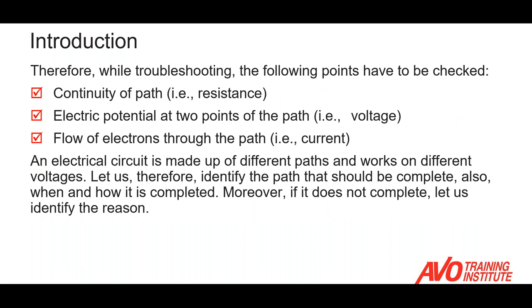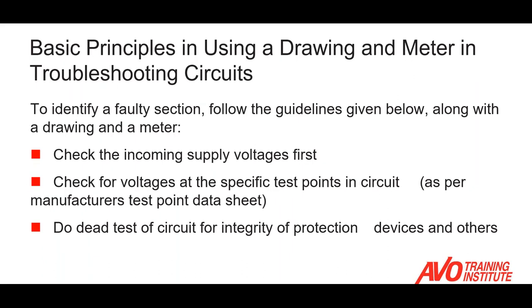For troubleshooting, we have to check the following points: continuity of a path, which is nothing more than a continuous electrical connection; our voltage — do we have a source?; and then the flow of electrons through the path. Electrical circuits are made up of different paths that can work on different voltages, so we need to be able to identify the path and how it's completed. If it's not complete, we need to identify the reason. The first thing we need to look at is: do we have an incoming supply? Is the voltage there? Is it correct? We need to check the voltage at specific test points per the manufacturer's data, and our engineered drawings that are site-specific will be a great help in troubleshooting.